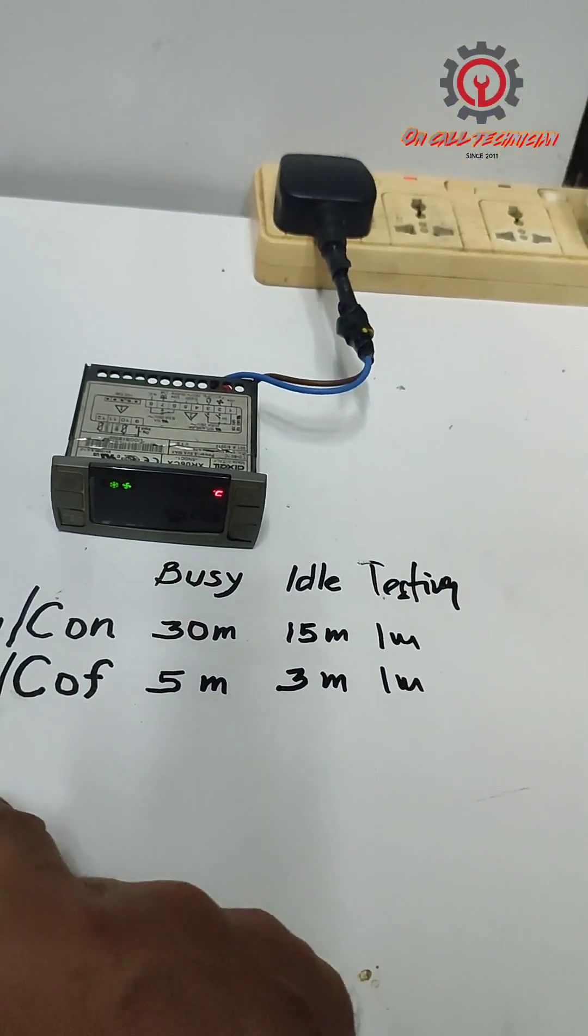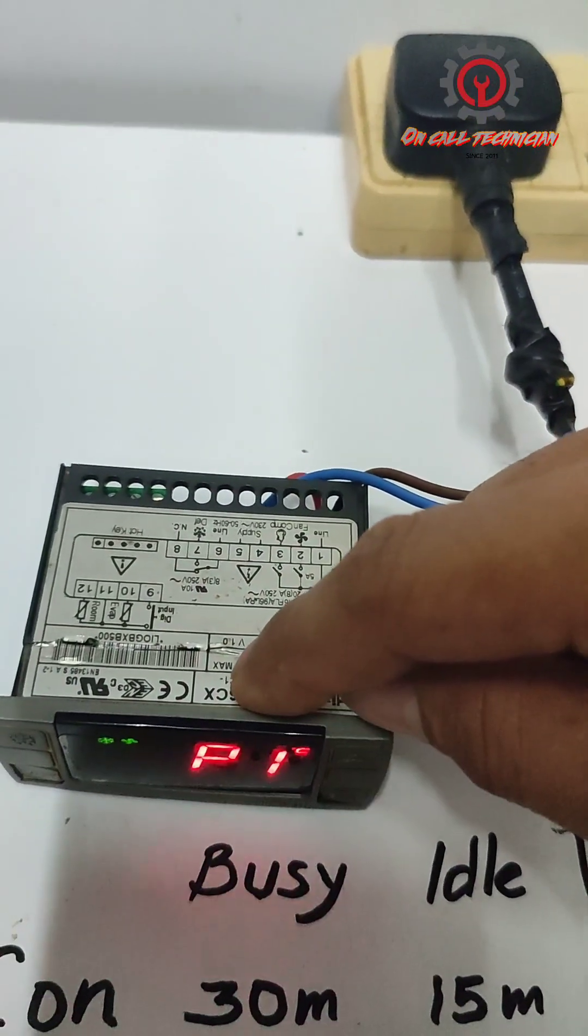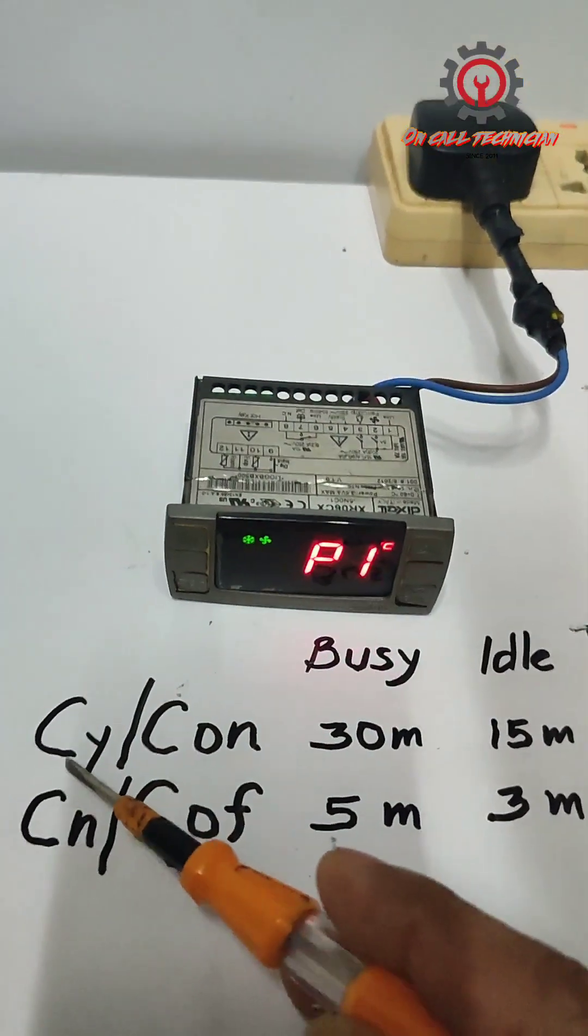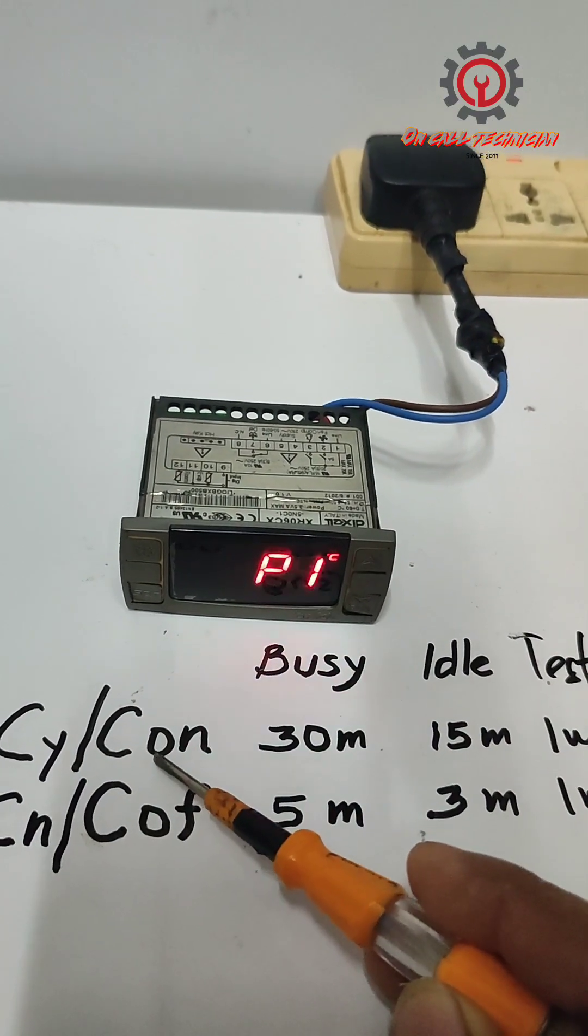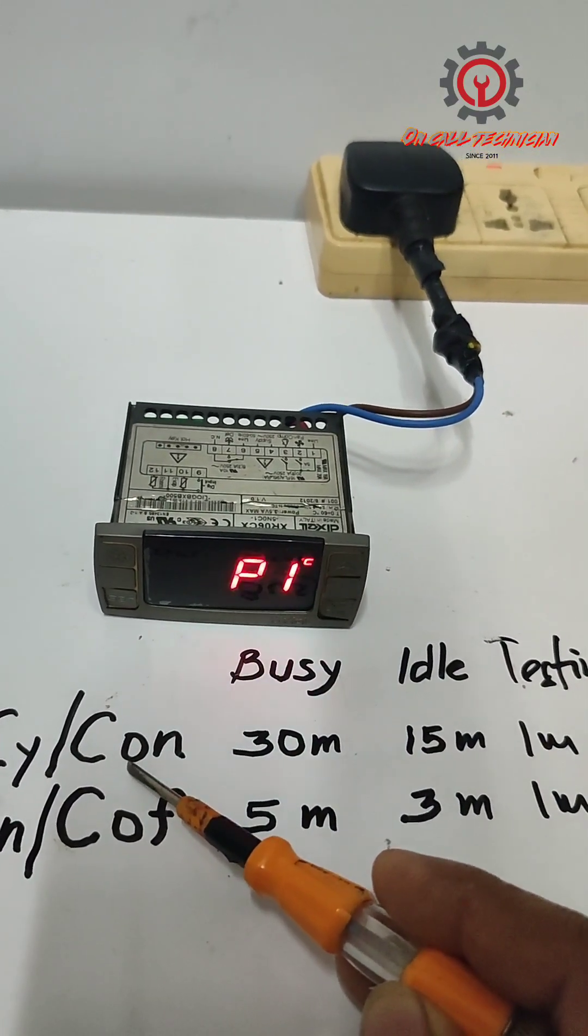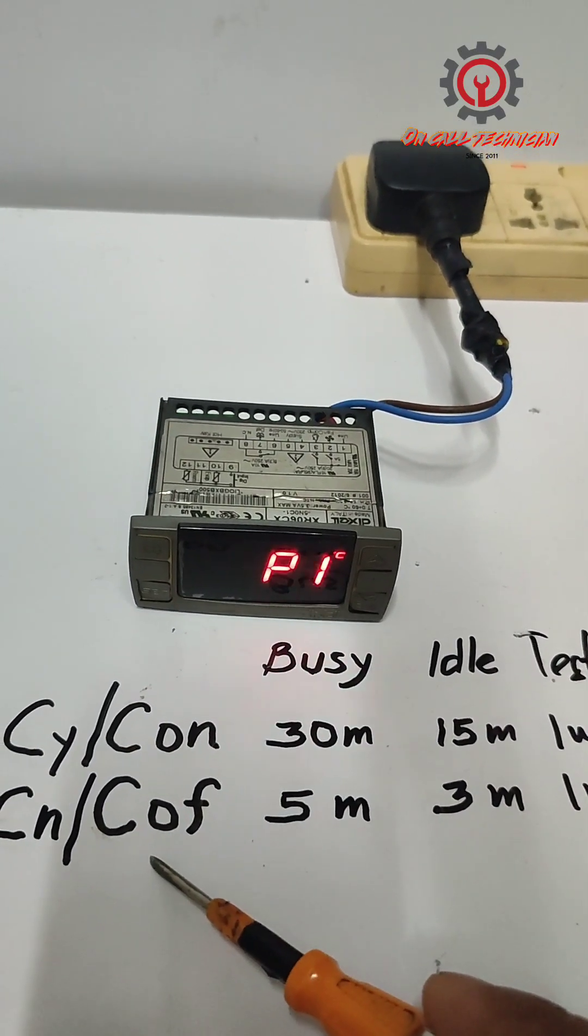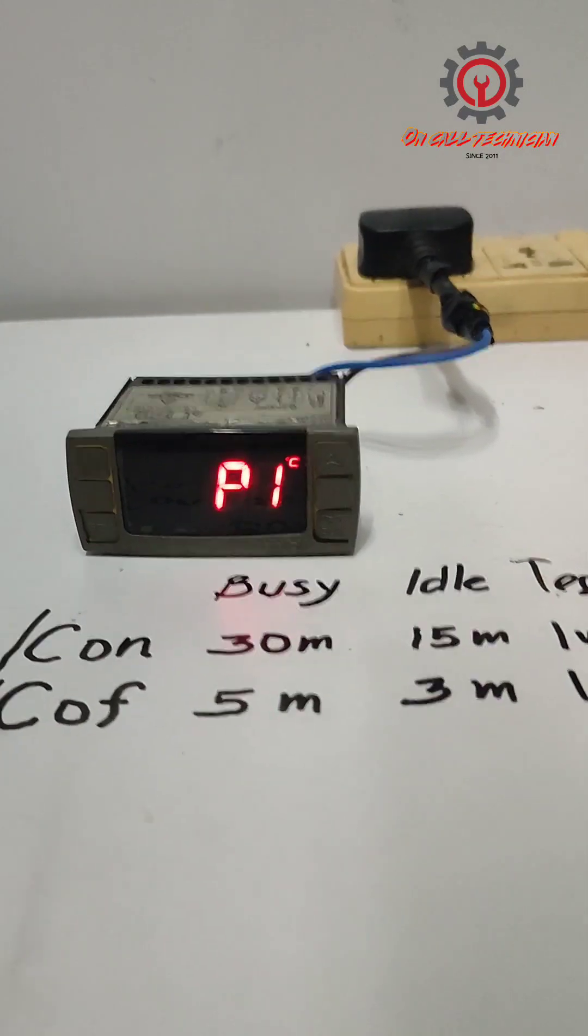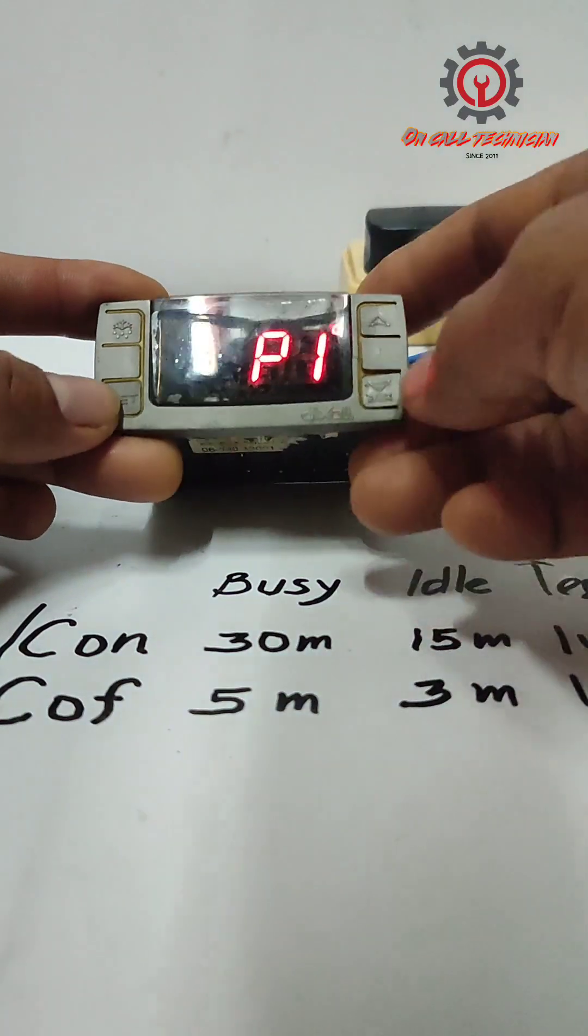The model I use here is XR06CX and the parameter for that is CY and C on. For other models of Dixell it's CN and C off for the cut off.